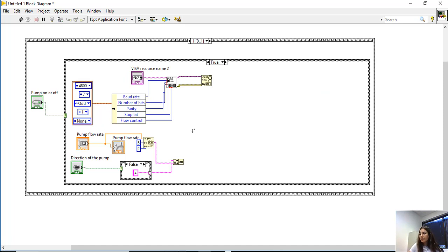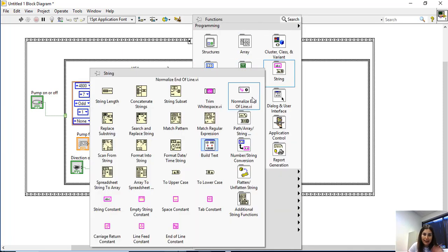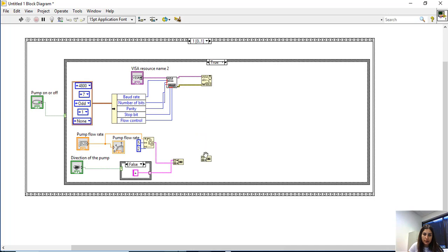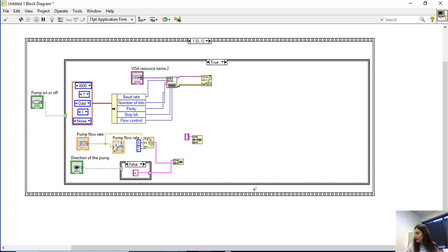So I will need to have another concatenated string because I have to add the other command too. And the other command is coming first, so I will create a constant backslash 02 P01 S, and that means set the pump flow rate, basically RPM, to this number. And then make sure that this is on remote order, so the pump is running remotely.